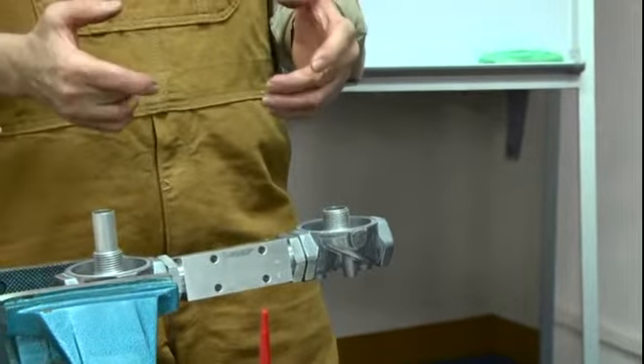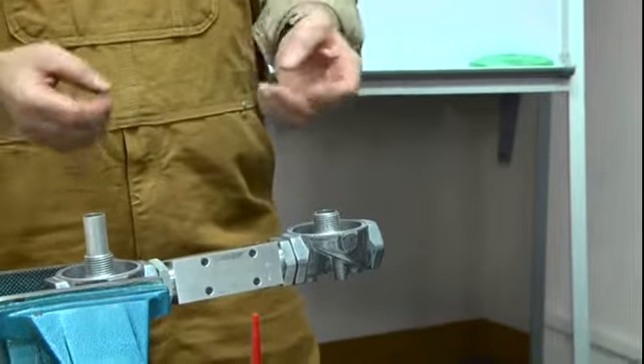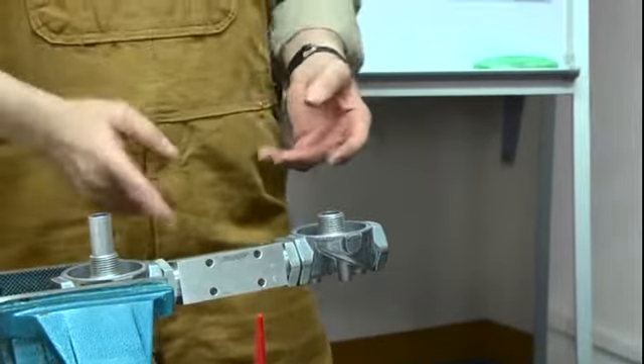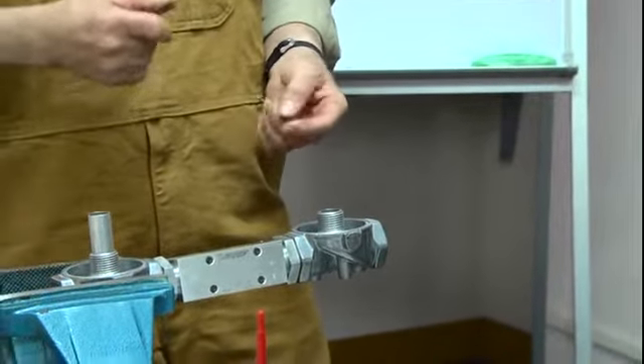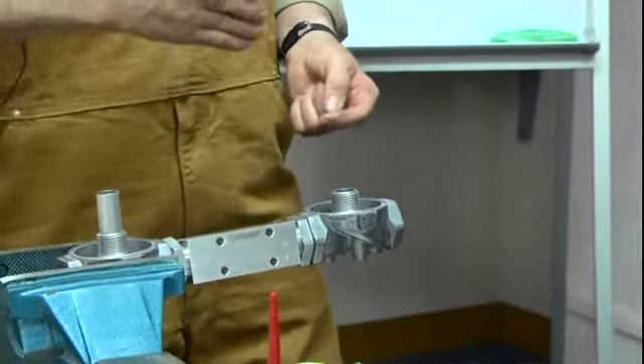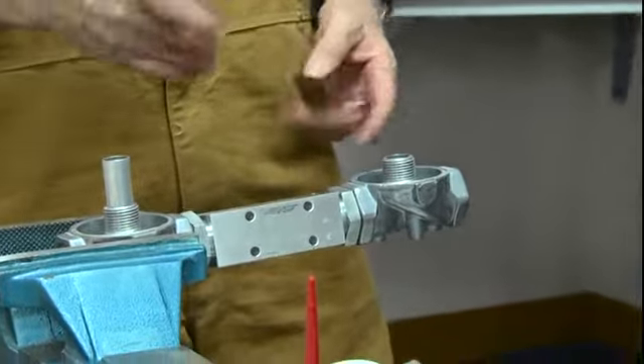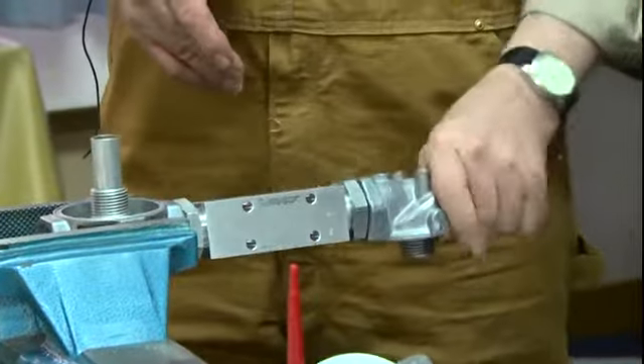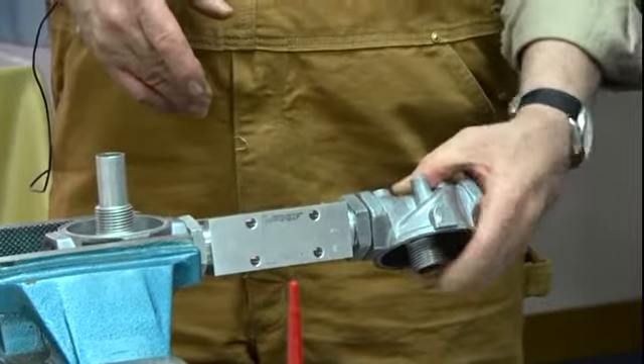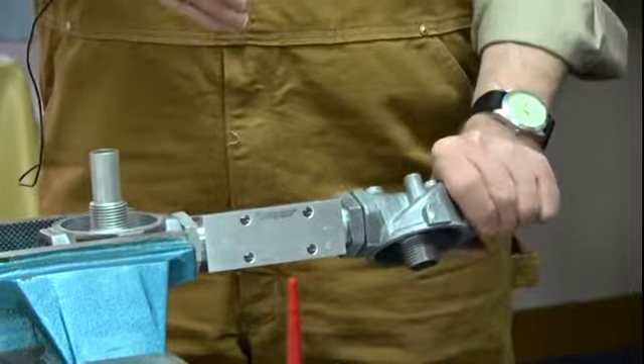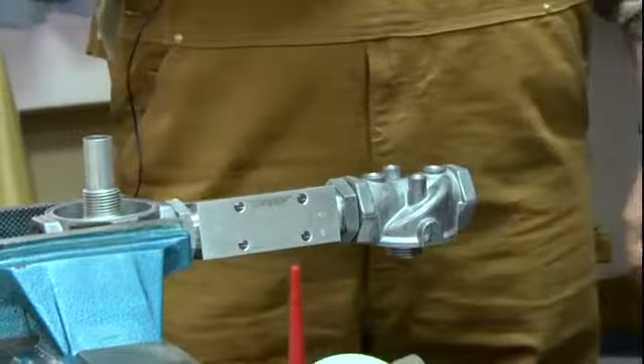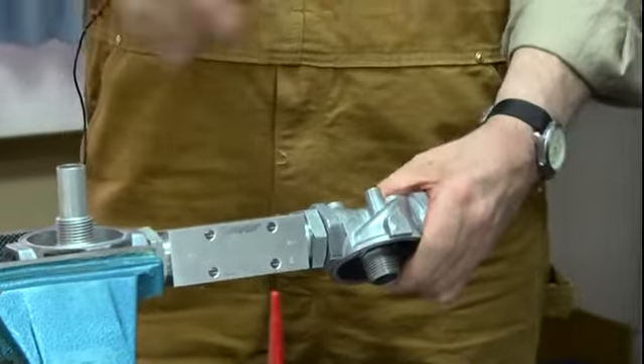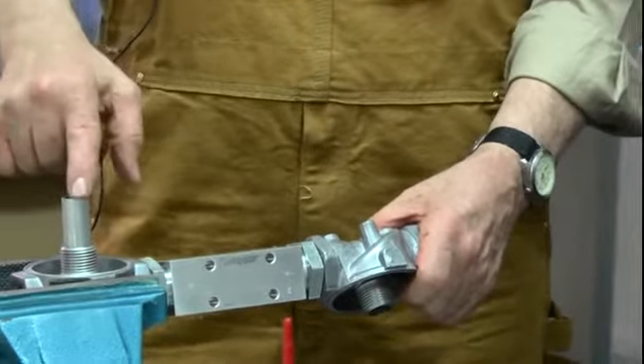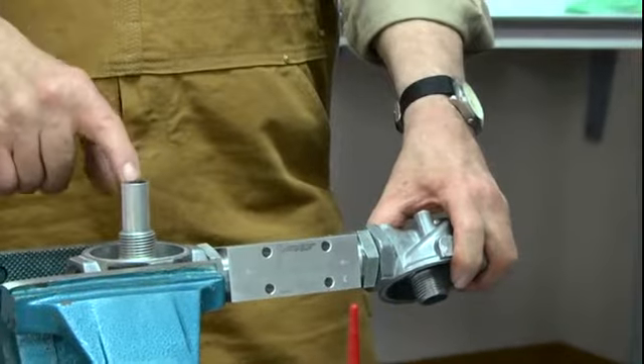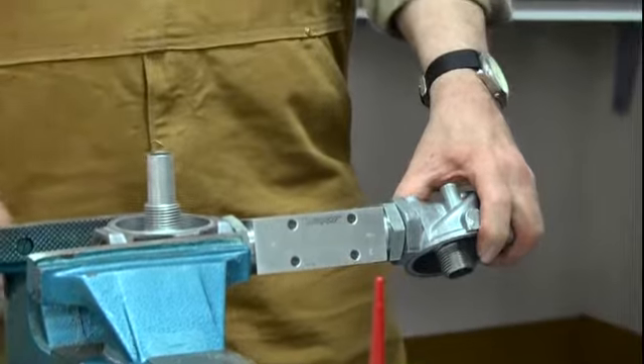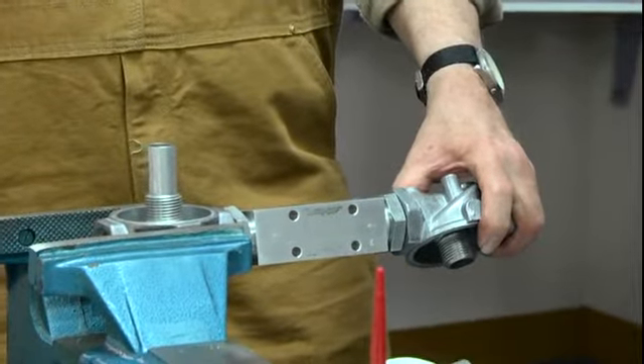Air is compressible, so they'll compress at different rates, okay? And it will drive the rotor and the sensor nuts. It will speed up, it'll slow down, it'll read high, it'll read low. You never do this. That's why you can go to about that point there, and that's fine. The pulsation damper, you can rotate it as well, but the more you rotate it, the less air that'll be trapped, the less vapors.